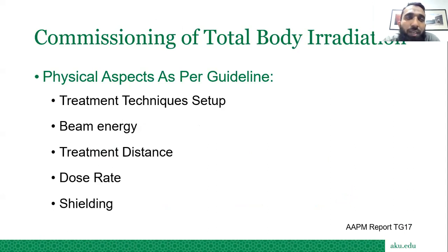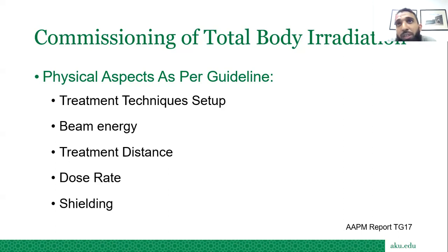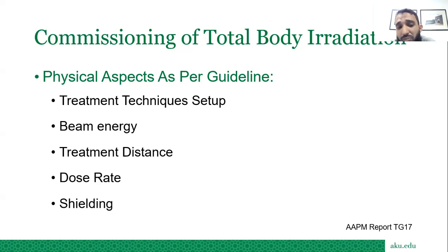For commissioning of total body irradiation, the AAPM report TG-17 suggests special considerations about physical aspects of treatment: what treatment technique to use to deliver uniform dose, what energy to use, what treatment distance is needed, at what dose rate to deliver, and which vital organs to shield during treatment.